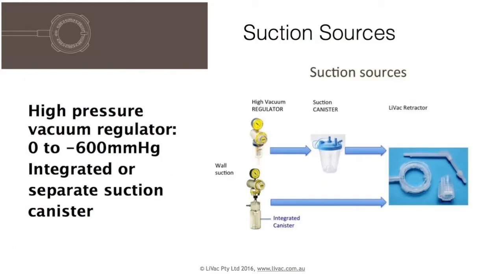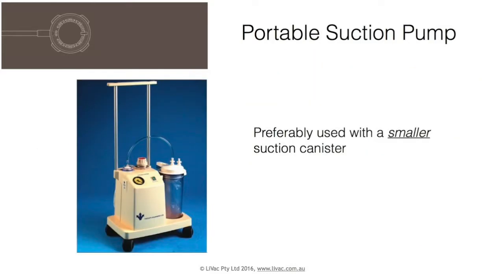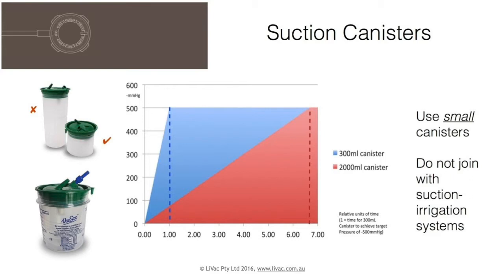High pressure regulators come with integrated or separate suction canisters. Many brands are available. They should be labelled for use with the LiVac Retractor and stored together. A portable pump may be used, preferably with a small canister. A vacuum is formed much more quickly with a small canister.